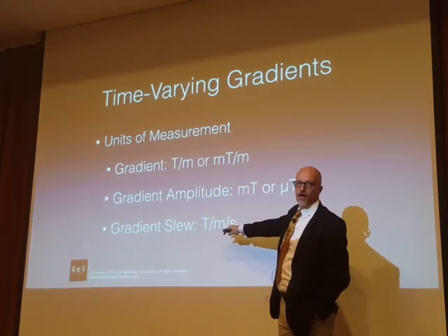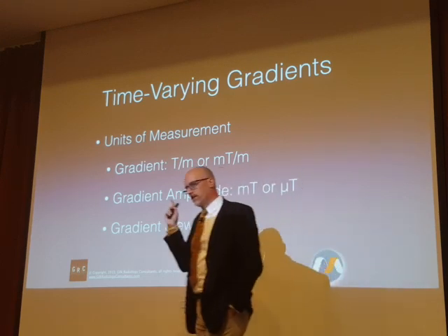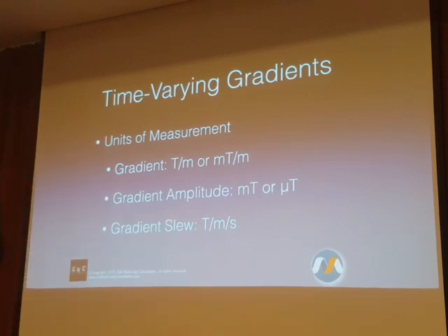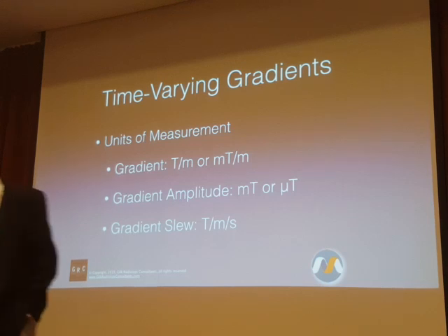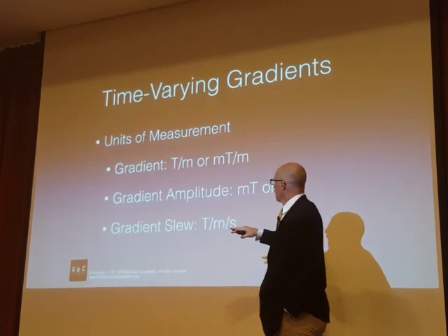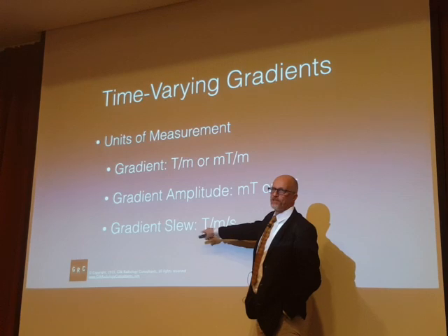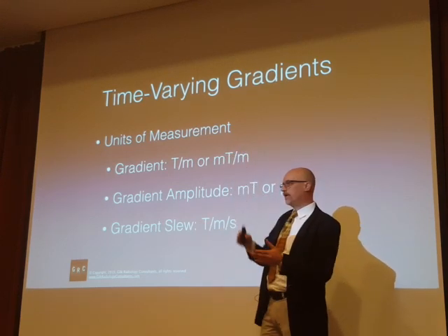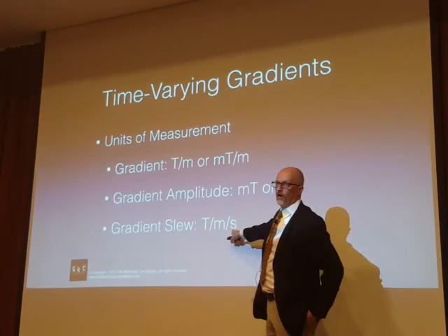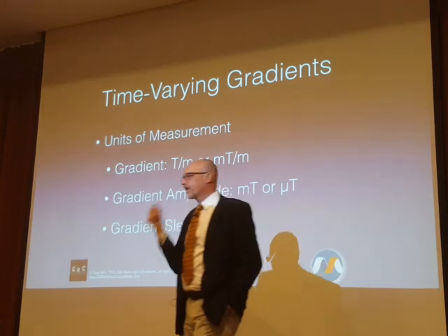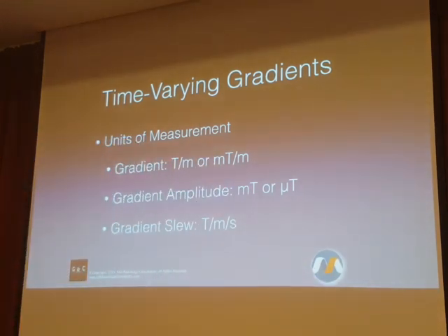And then the third element, and this is really, quite honestly, the only one we care about, is the slew rate. This is the only one we care about in terms of direct neuromuscular stimulation, and also the loudness that's created during the gradient portion of this. What we care about is what is the maximum change in amplitude over distance over time. The slew rate, the combination of the maximum, the degree of amplitude change over a shorter and shorter duration. That's what triggers neuromuscular stimulation.